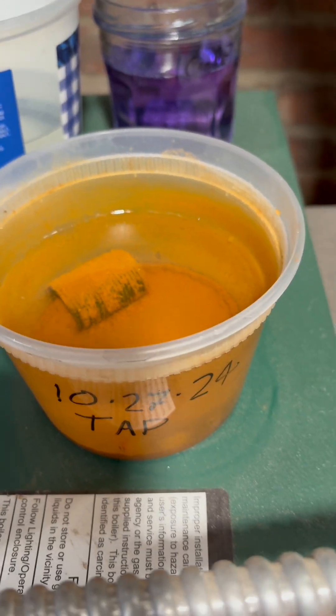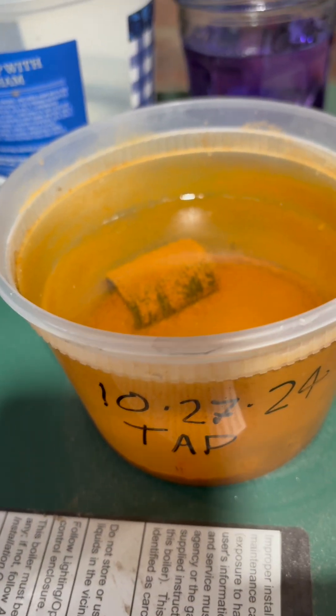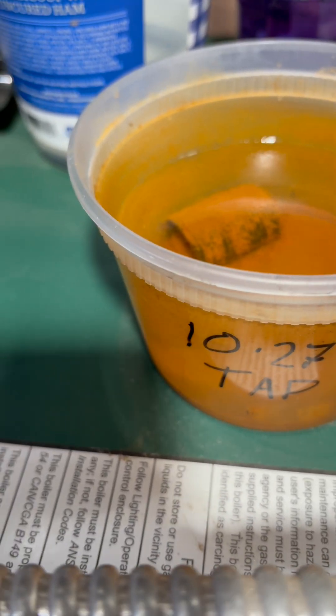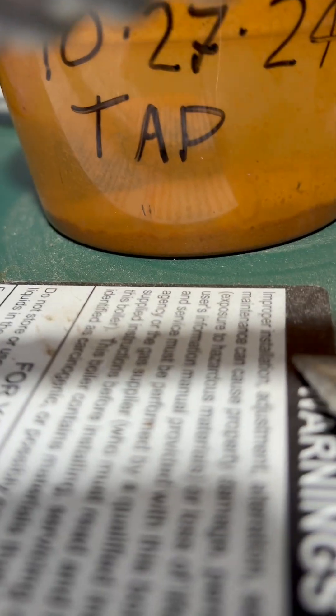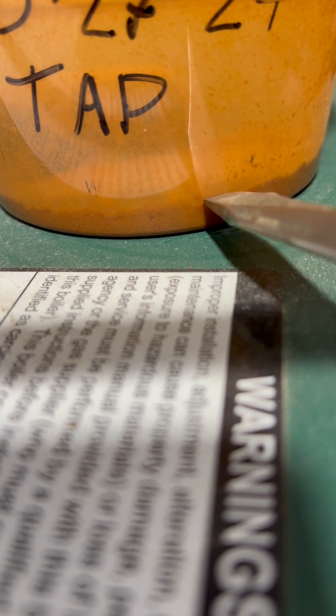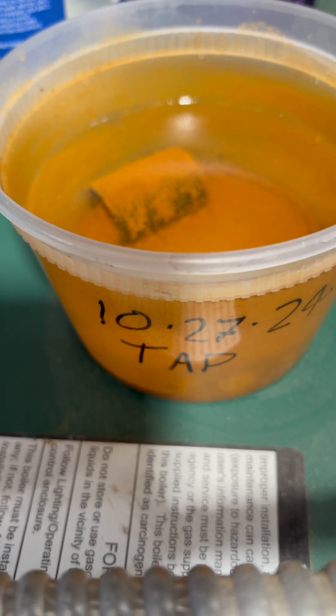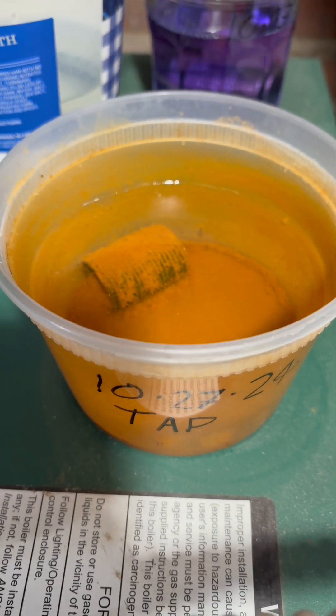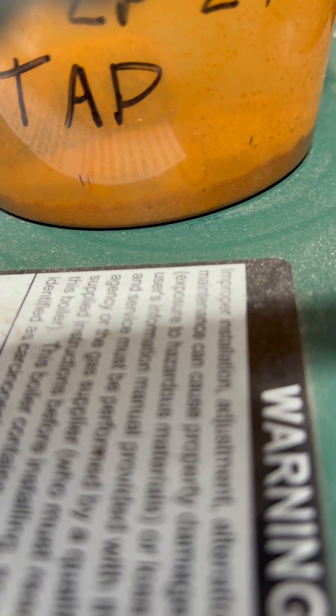This one, what I did here is I put these on my boiler so they'd get some heat and maybe the water would evaporate a little faster. And when the water level starts to drop, I just top it off with my tap water. And I've done that over this month. I've done it four or five times. You can see at the bottom here, there's a good quarter inch of powdery rust sediment that has formed there. Now that doesn't mean this fitting is totally rusted out. Rust gets generated in a lot greater mass. A piece of steel doesn't have to rust very much to create like a lot of rust. And that's what we're seeing here. This is very silty. I'll stir it up here in a minute, but it's very silty.